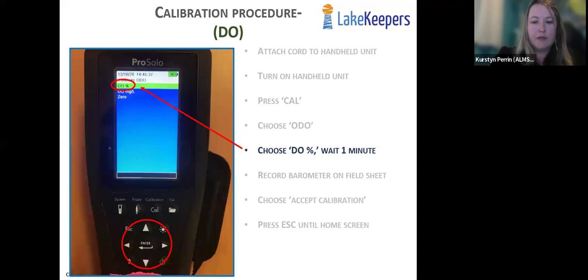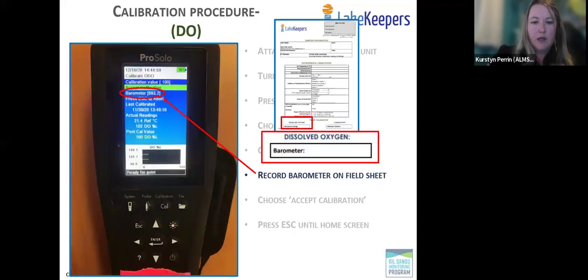Again, choose the first one, the DO %. And it's going to bring you to the screen. You can see the little black box at the bottom with 2 lines. So we just want to give that a minute to calibrate and acclimate. We want to make sure the lines are steady, that there's no sudden peaks on it. And then this is also an opportunity to record your barometer reading onto your field sheet. So that's just at the bottom of your field sheet, and you can find the barometer reading here.